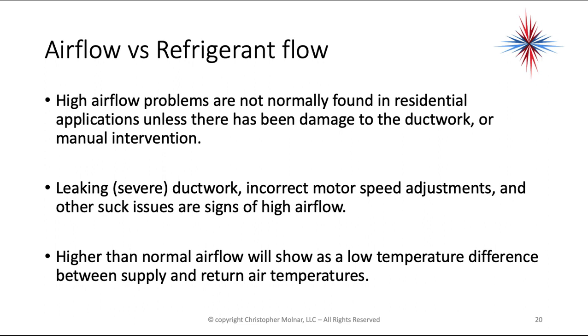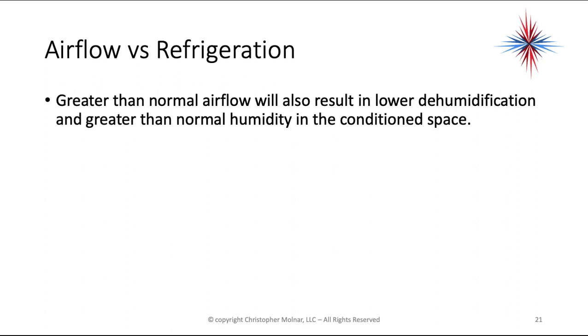High airflow problems are not normally found in residential applications unless there has been damage to the ductwork or manual intervention. Severely leaking ductwork where pieces are missing, incorrect motor speed adjustments, and similar issues are signs of high airflow. Higher than normal airflow will show as a low temperature difference between supply and return air temperatures, and will also result in lower dehumidification and increased humidity in the conditioned space.